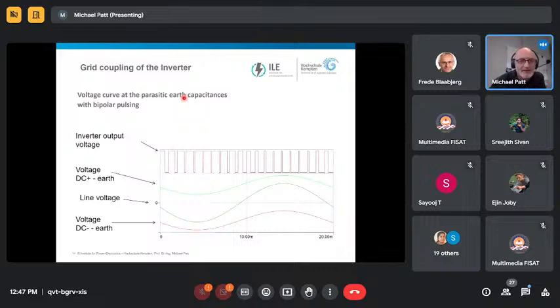When we do everything right here, we see the voltage curve of the parasitic earth capacitance in bipolar pulsing: the inverter output between plus and minus, and the upper and lower capacitor voltages, with the grid in between. The distance here is the PV voltage, and the sinus on top is half of the grid voltage.